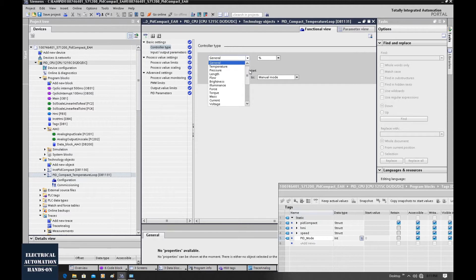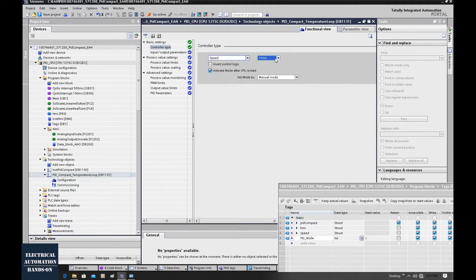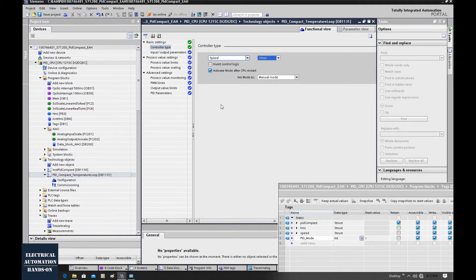For example, if this PID loop is used to control speed, we can select speed control. Also, from here you can select the unit. This invert control logic is very important. If you are controlling a heater system and increasing the heater energy causes the temperature to go higher, you do not need to select this checkbox. But if you are controlling a cooling system — where increasing the output causes the temperature to go down — you need to check this invert logic checkbox.